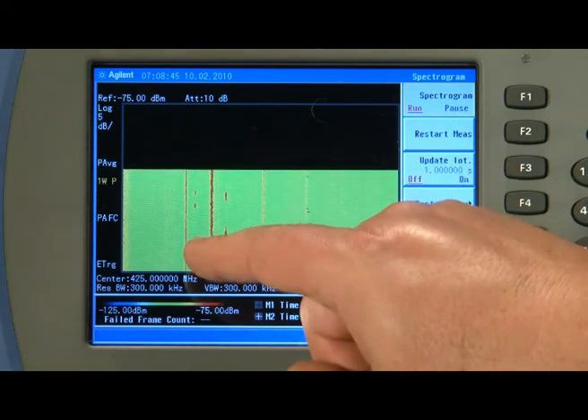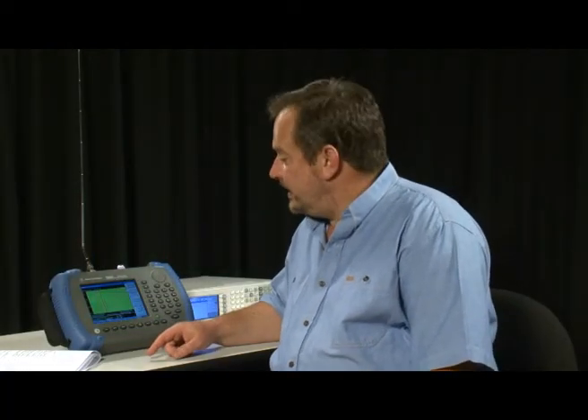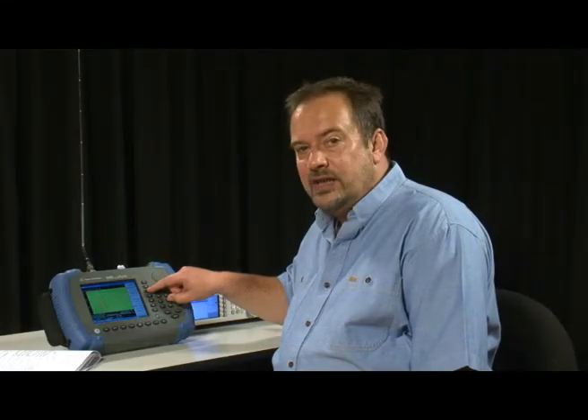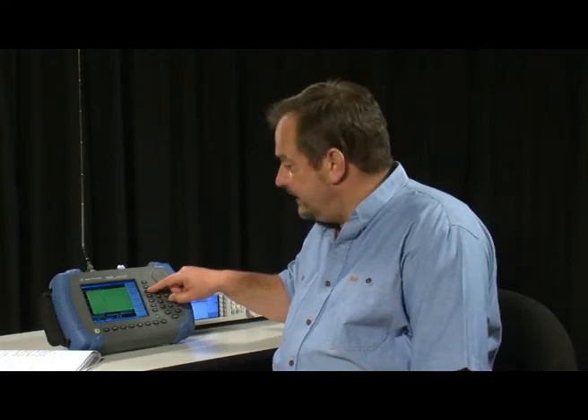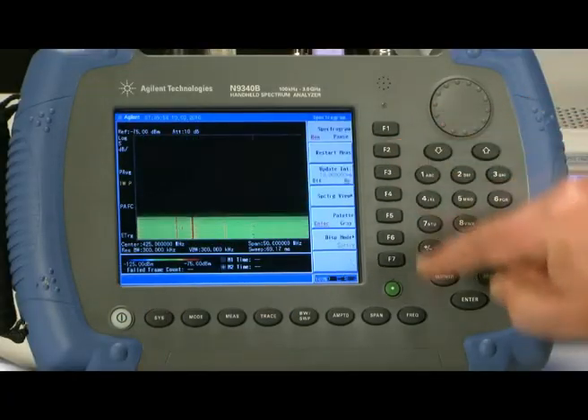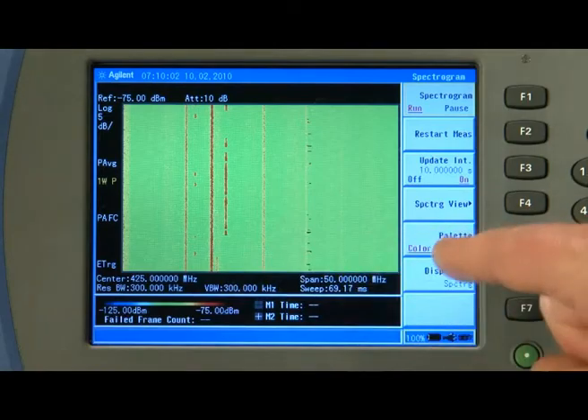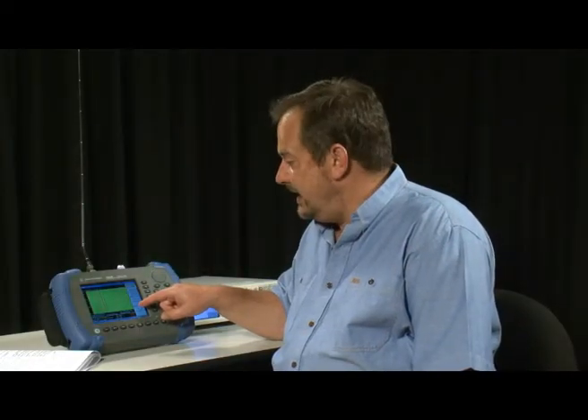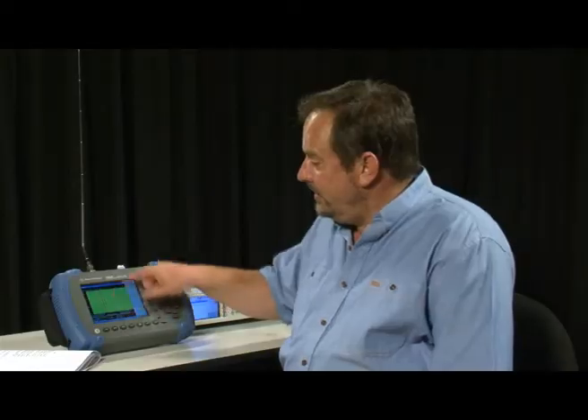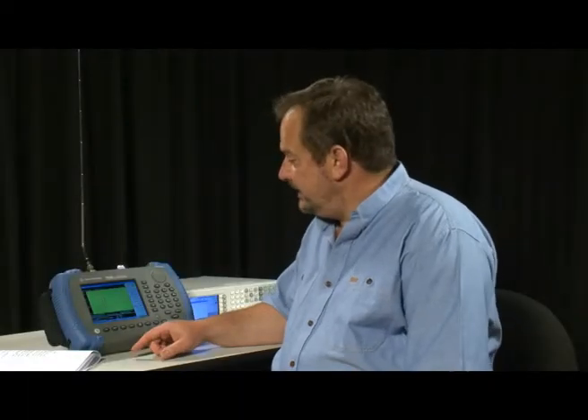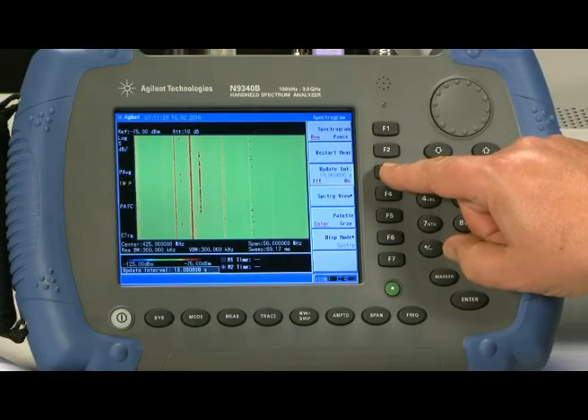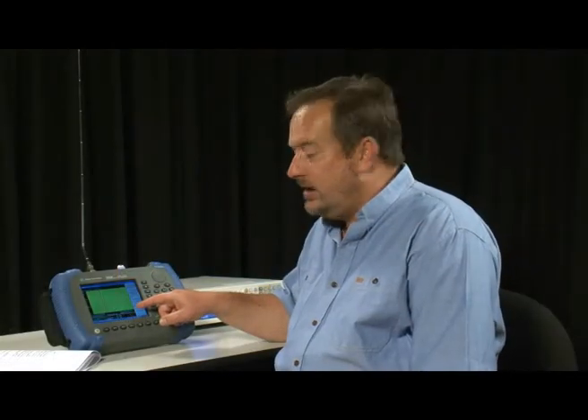Now I can change the update interval for the spectrogram measurement by pressing the Update Interval button. Now let's say I only want to capture a trace every 10 seconds. I can type in 10 seconds and now each new sweep will be performed after a 10 second delay and added to the collection of traces that make up the spectrogram. Let me set the Update Interval back to OFF so the trace will now update as fast as it can.